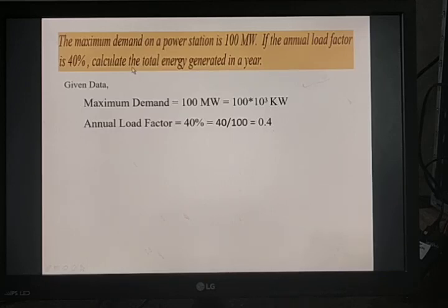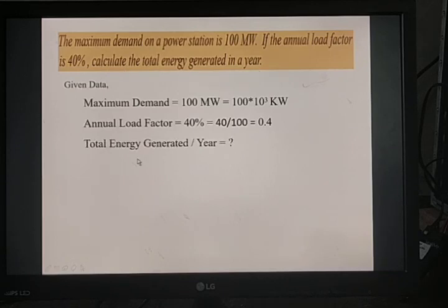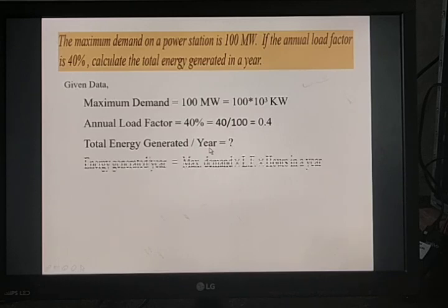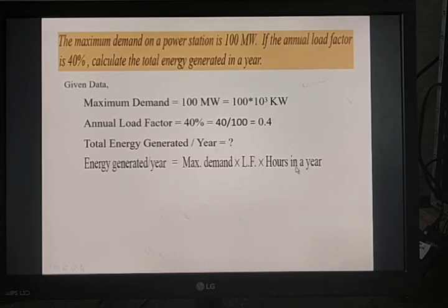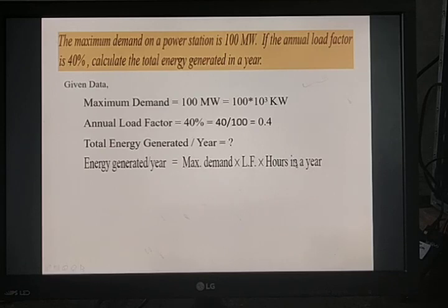We need to find the total energy generated in a year. Energy generated per annum equals the product of maximum demand, load factor, and hours in a year. The maximum demand is 100 × 10³, load factor is 0.4, and hours in a year is 8,760 — that is 365 days times 24 hours.